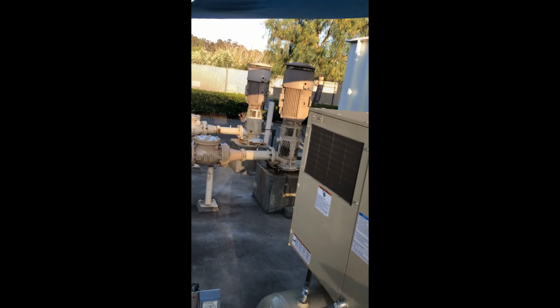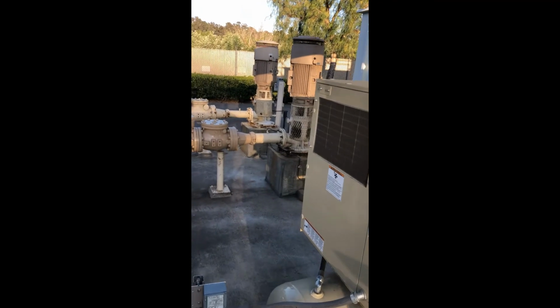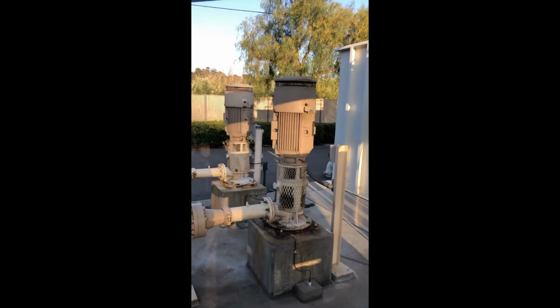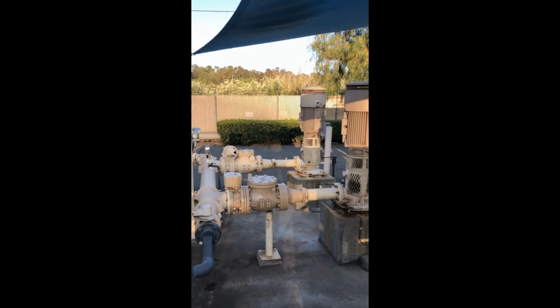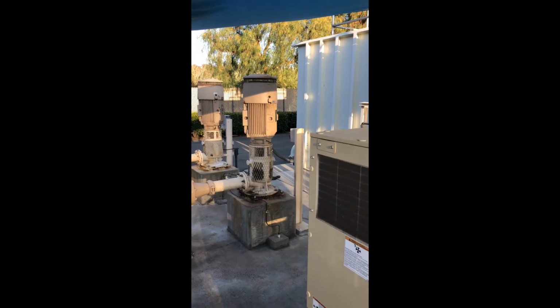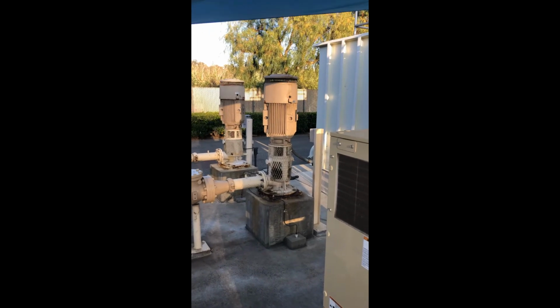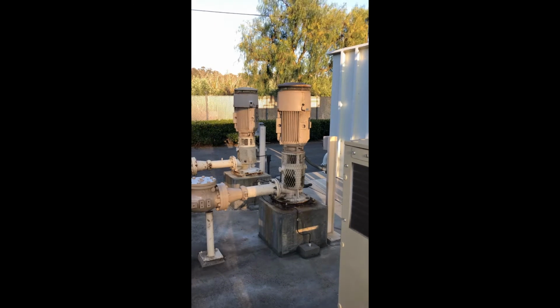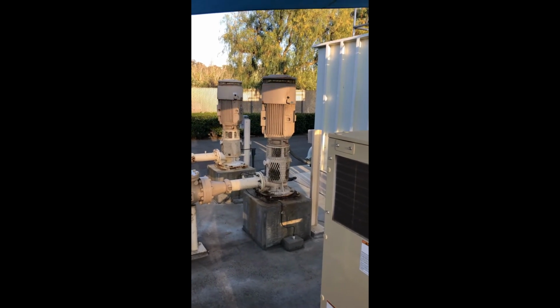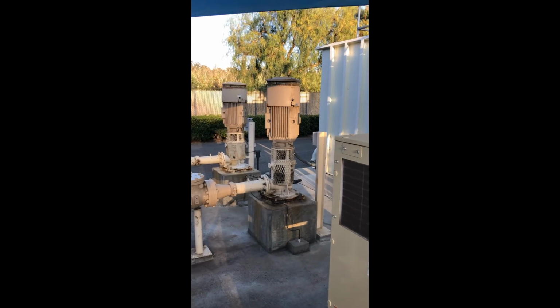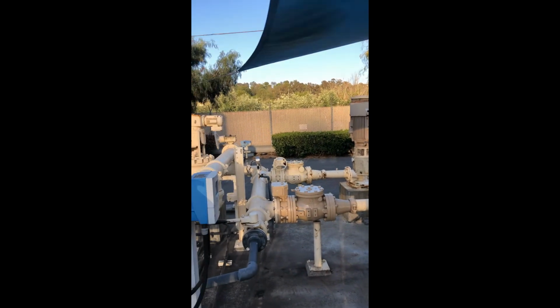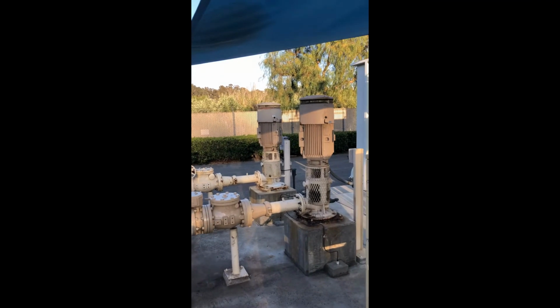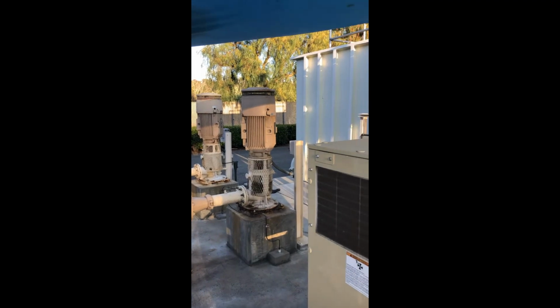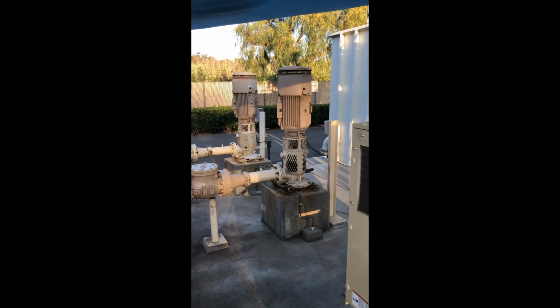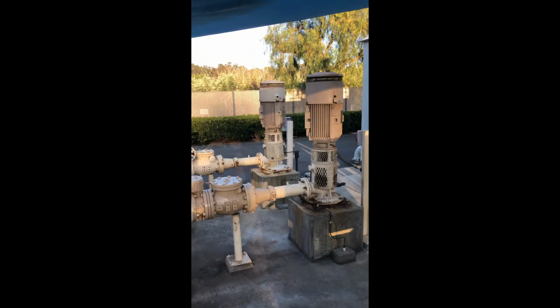They call this the applied wet well. And so we have a couple of things going on here. This is a good location for these pumps. They call these the 3W pumps. What they do is take that clean water and pump it through a system throughout the plant that we can use to hose things off with. We use it for seal water for our pumps. There's a whole list. They use it for the dewatering, to mix the polymer. There's a lot of what they call utility water use, where we need water internally at the plant for a variety of different purposes. And so that's what these pumps here do.